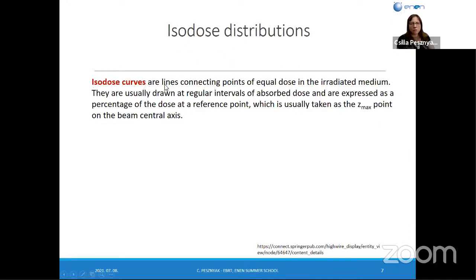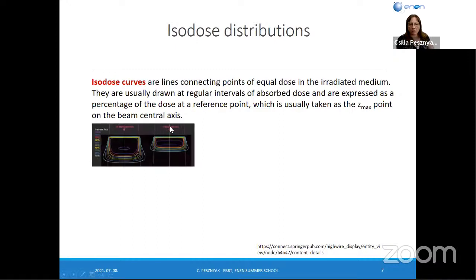We use the isodose curve, and these are lines connecting points of equal dose, it is very important, in the irradiated medium. They are usually drawn at regular intervals of absorbed dose and are expressed as a percentage of the dose at a reference point, which is usually taken as the Zmax point on the beam central axis. Here you can see the isodose curves for the electron. If we have a larger energy, here is a 16 mega electron volt energy, the Dmax is deeper, and the isodose curves are deeper. And here you can see the 9 mega electron volt electron. And it's very interesting that these curves go out of the field. They have a bigger scatter than in photon cases.